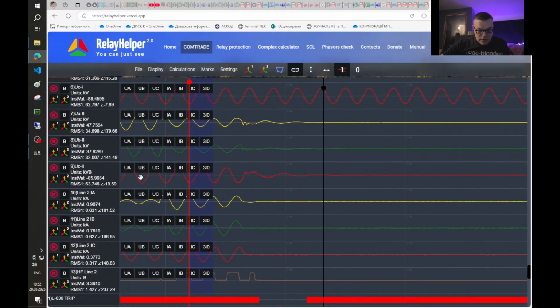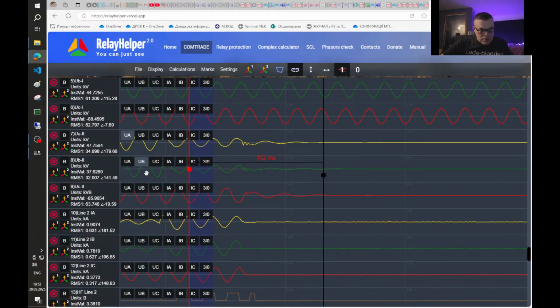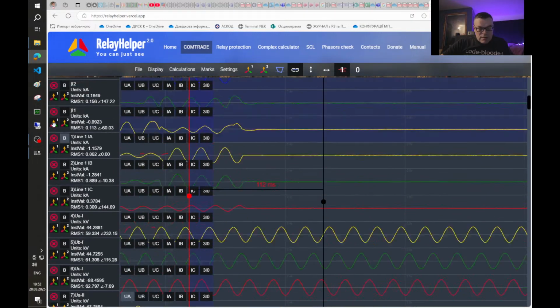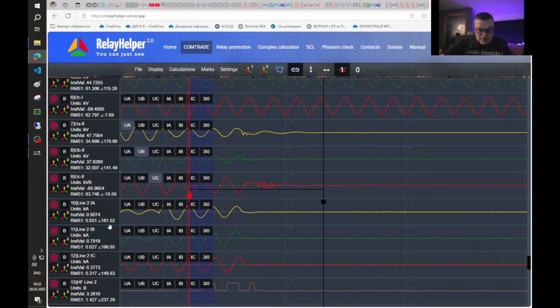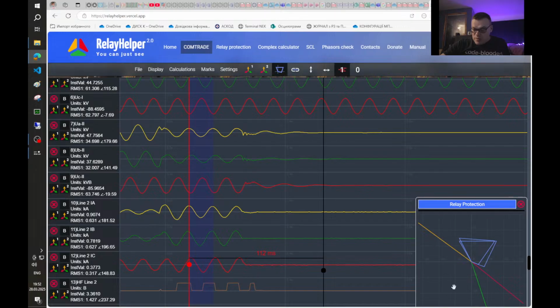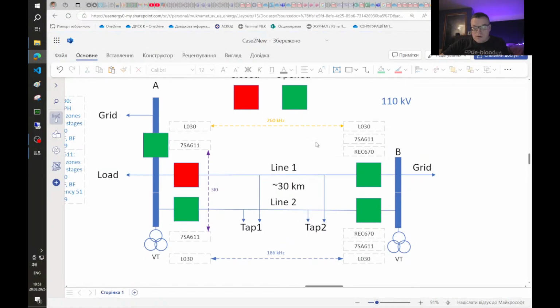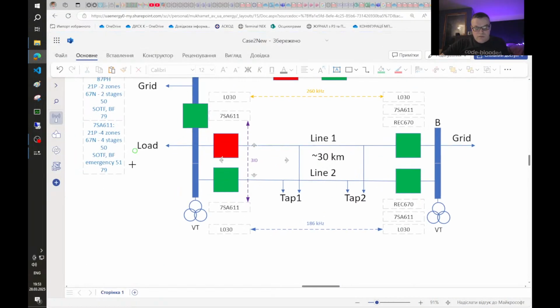So here are our voltages, and let's start with the second line, because we found that the second line was tripped by phase differential protection, and let's check whether distance protection was able to trip. So as we can see, no. So why is that?